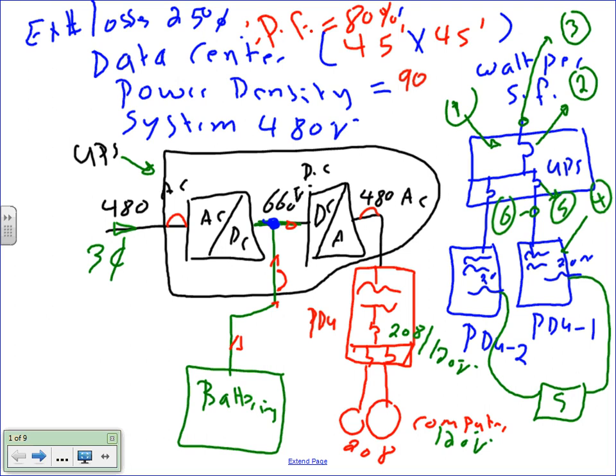Any question about how the riser is put together? What we need to size? Right? So basically the PDU and the UPS, the feeder to the PDU and the feeder to the UPS, the overcurrent protection device to the PDU and the overcurrent protection device to the UPS. PDU stands for power distribution unit, nothing other than a fancy name for a big transformer and a 42-circuit three-phase panel in the same enclosure. That's it. That's what a PDU is. Because a panel typically has no transformer in it, unless it's a substation. If you put a transformer inside the panel, they call it a power distribution unit. One name for it. Okay, any question guys about this, the system?